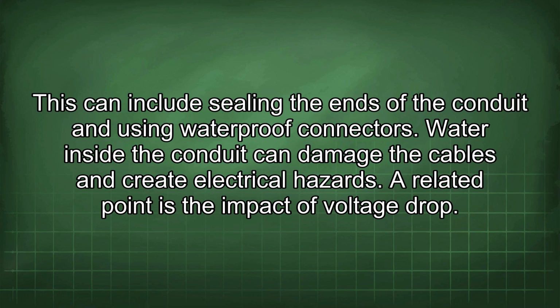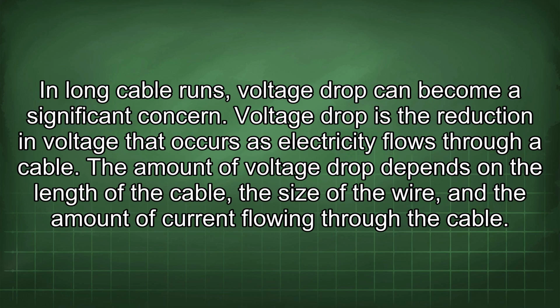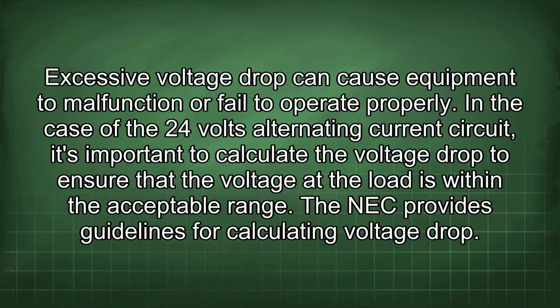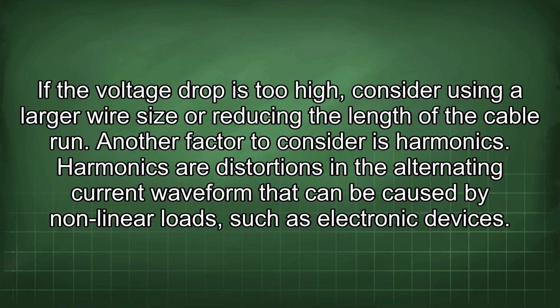A related point is the impact of voltage drop. In long cable runs, voltage drop can become a significant concern. Voltage drop is the reduction in voltage that occurs as electricity flows through a cable. The amount of voltage drop depends on the length of the cable, the size of the wire, and the amount of current flowing through the cable. Excessive voltage drop can cause equipment to malfunction or fail to operate properly. In the case of the 24 volts alternating current circuit, it's important to calculate the voltage drop to ensure that the voltage at the load is within the acceptable range. The NEC provides guidelines for calculating voltage drop. If the voltage drop is too high, consider using a larger wire size or reducing the length of the cable run.